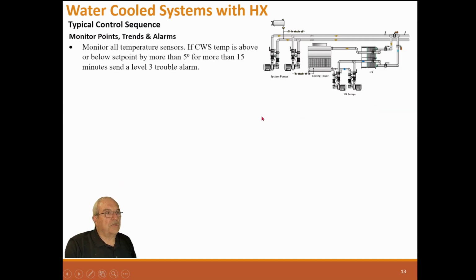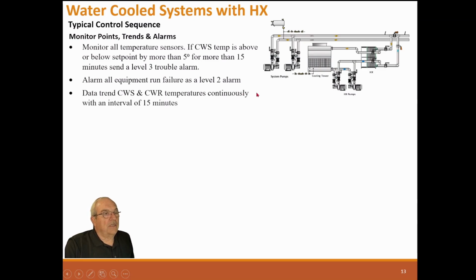Monitor points, trends, and alarms. Monitor all temperature sensors. Condenser water temperatures above or below set point by more than 5 degrees for 15 minutes sends a level 3 trouble alarm. Alarm all equipment run failures, level 2 alarm. Data trend condenser water supply and condenser water return temperature continuously with an interval of 15 minutes.